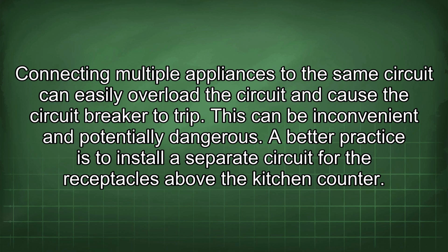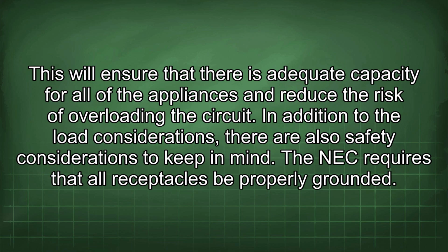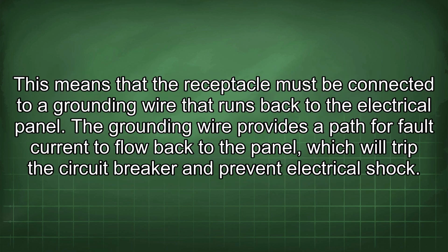A better practice is to install a separate circuit for the receptacles above the kitchen counter. This will ensure that there is adequate capacity for all of the appliances and reduce the risk of overloading the circuit. In addition to the load considerations, there are also safety considerations to keep in mind. The NEC requires that all receptacles be properly grounded. This means that the receptacle must be connected to a grounding wire that runs back to the electrical panel. The grounding wire provides a path for fault current to flow back to the panel, which will trip the circuit breaker and prevent electrical shock.